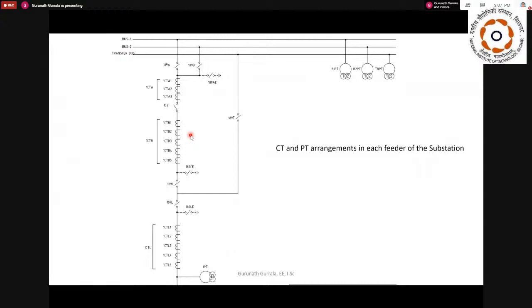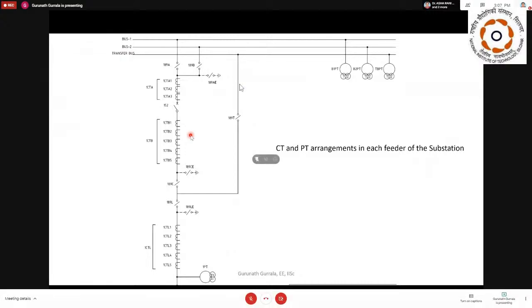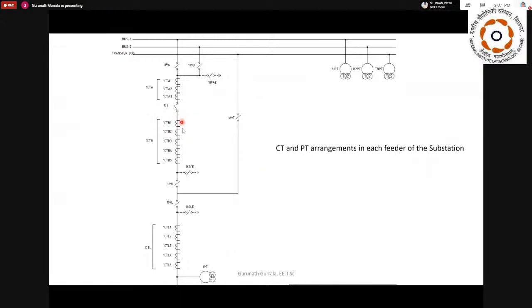So what we did is we used single primary CTs, that is, a single primary and a single secondary CT, 5 numbers, so that I can create just like a 5-core CT. So this can be treated as a 5-core CT, and this can be treated as a 3-core CT on one side. And you can also see this is the feeder, 1 feeder, and it also has feeder CTs, which are again treated as a 5-core CT.